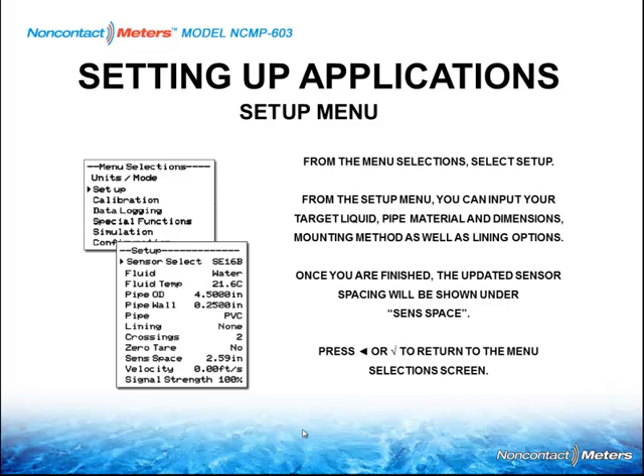Again, 95% of the time, you've got a Schedule 40 pipe, carbon steel. If you've got a copper tube, type L is the most common, and use the ANSI pipe chart books for this. Again, anything special on that, you have the ability to calculate that out. Look to the left, look to the right, look at fittings inside the pipeline that you're working with, which will pretty much tell you what size pipes you're working with here.